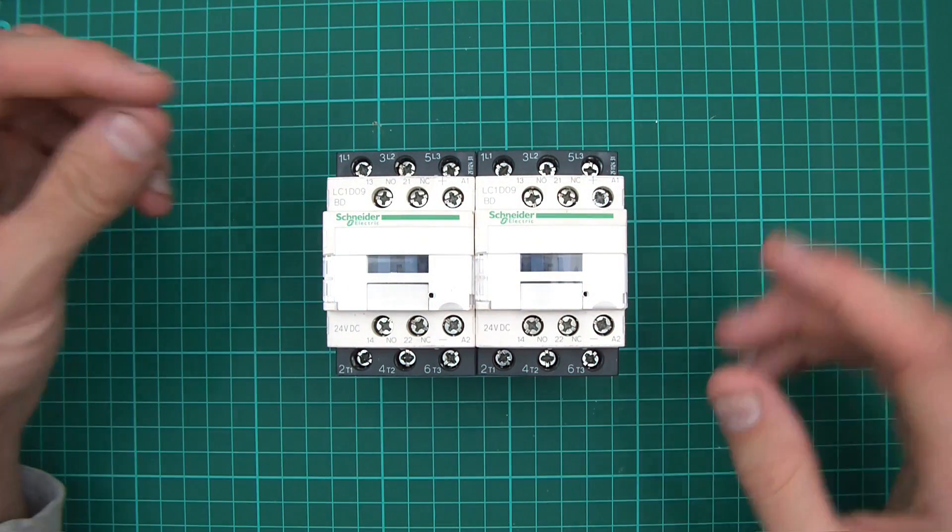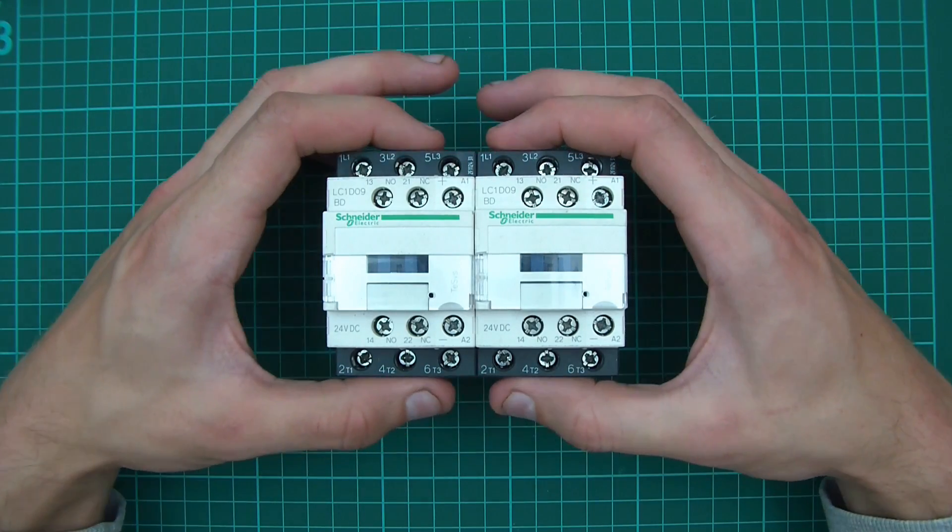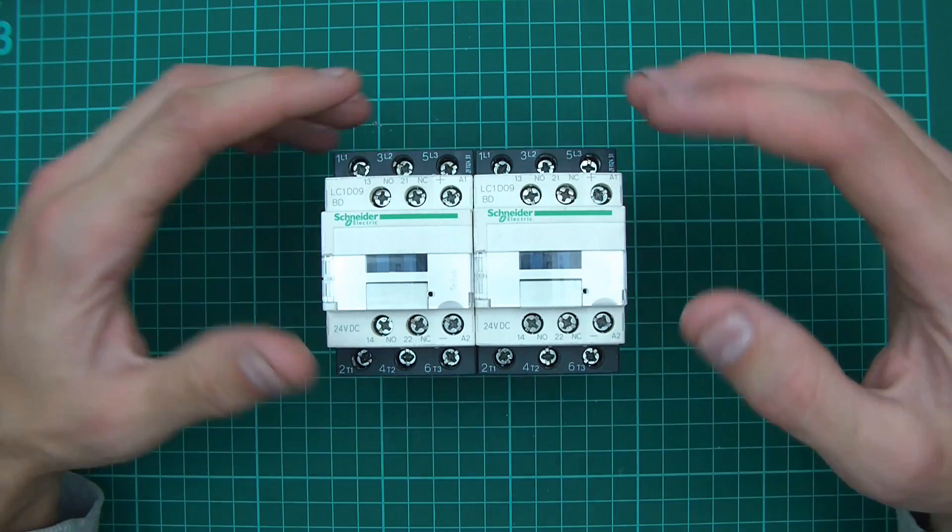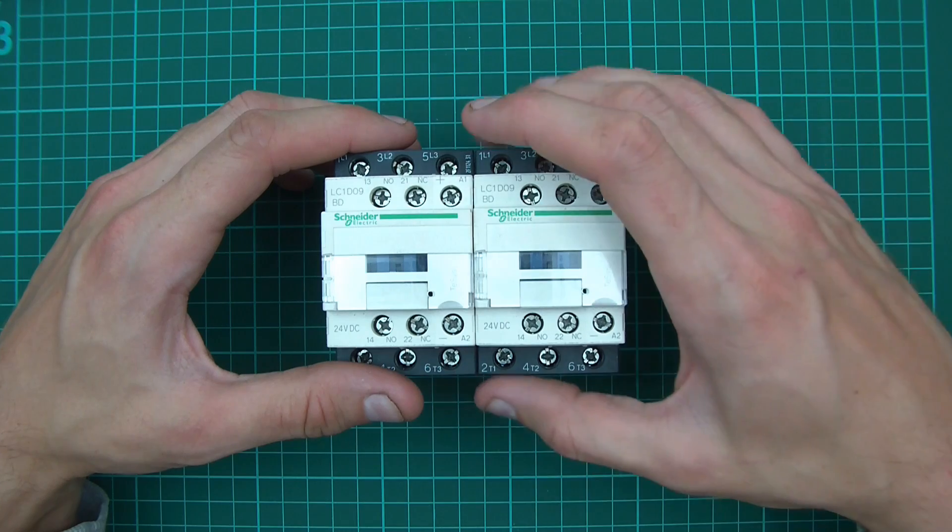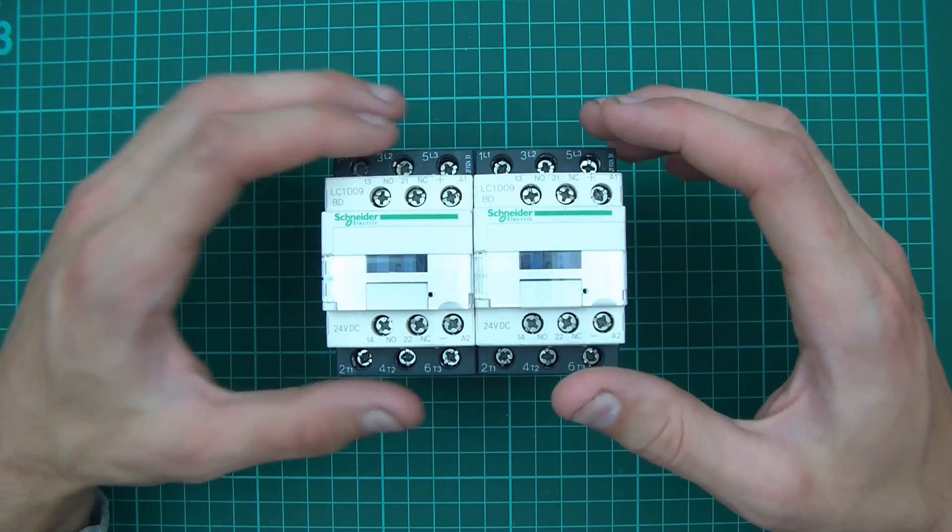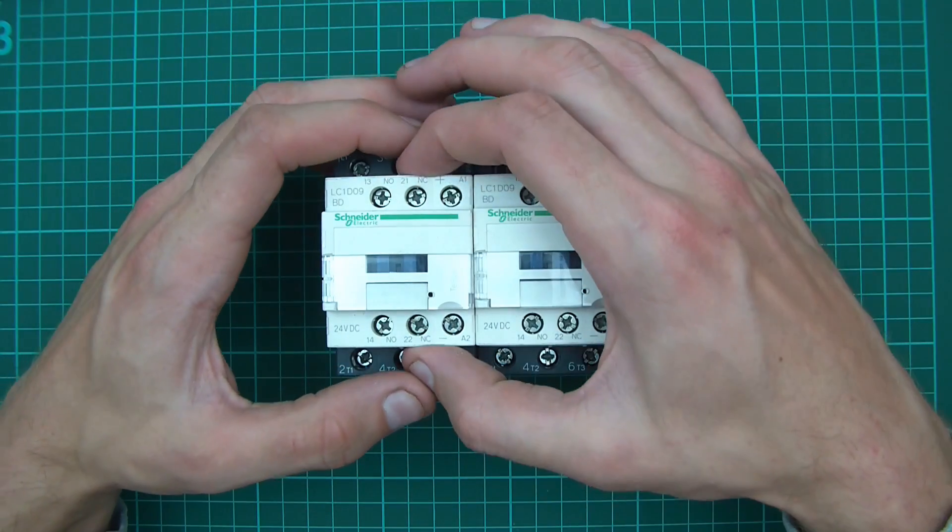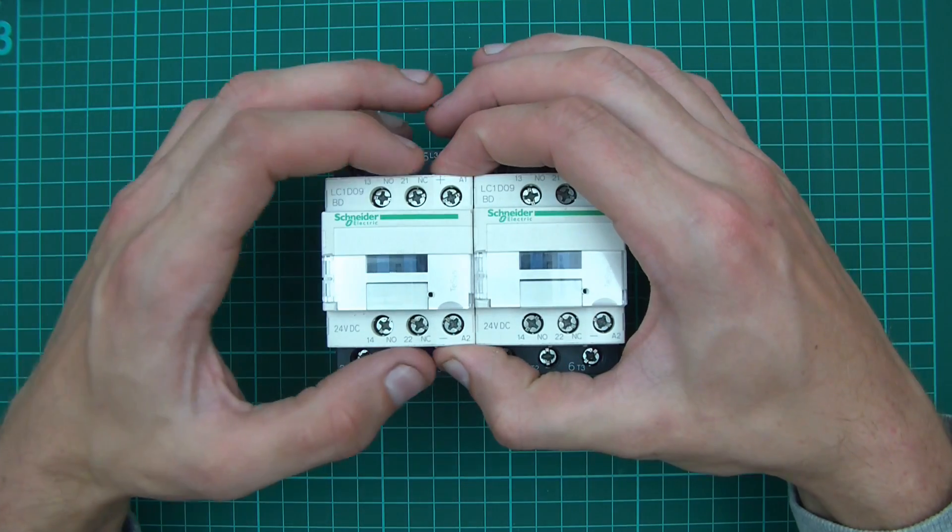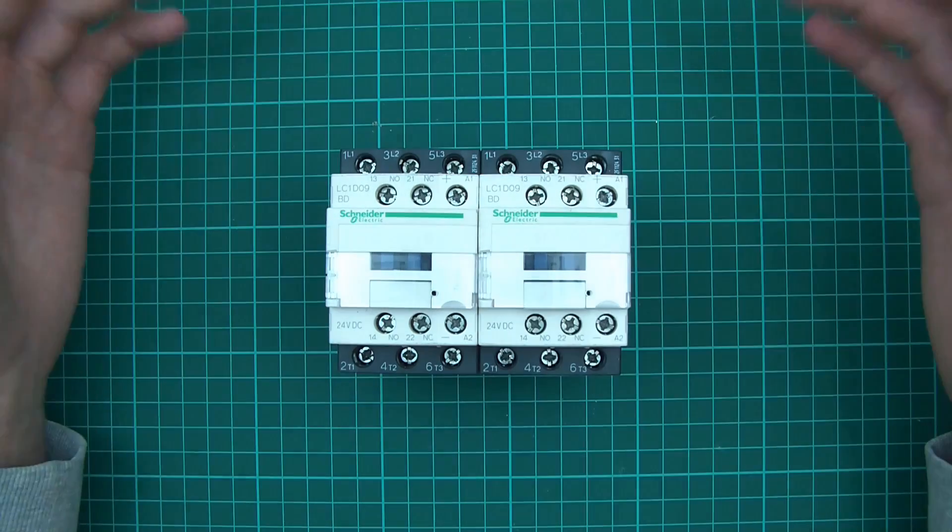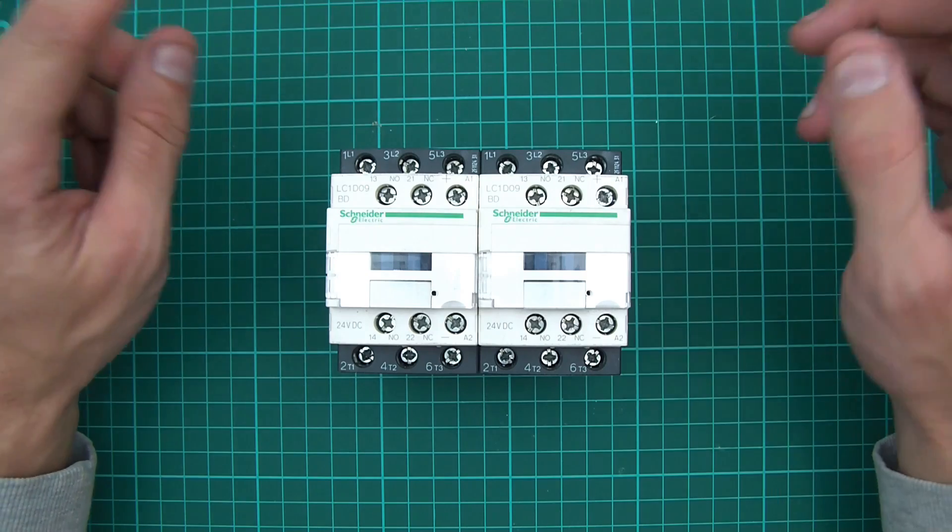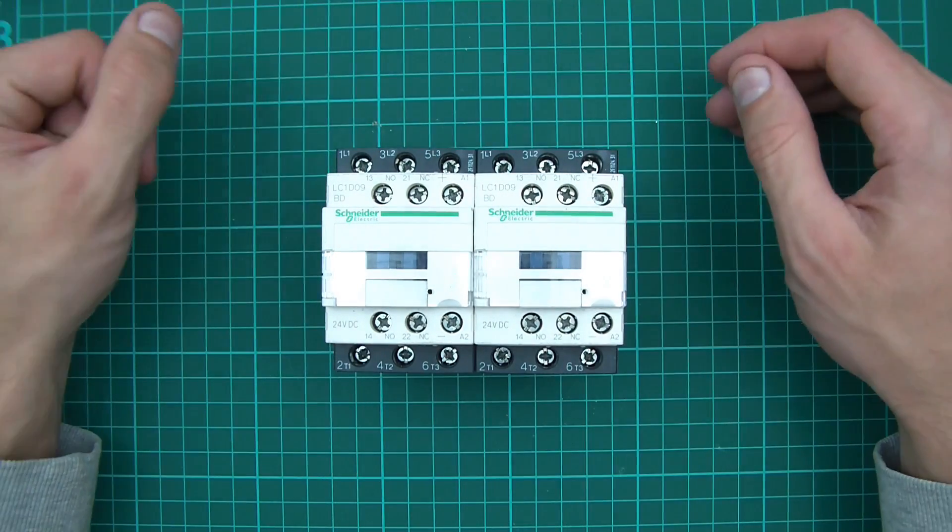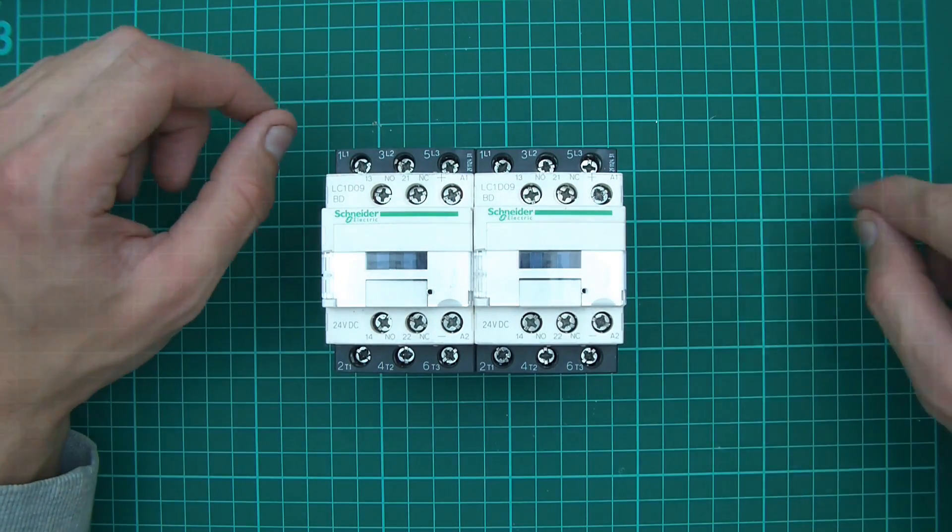These contacts here are called NO contacts or normally open contacts, and that means when there's no power to the coil these are open circuit. But there's one that says NC and that means normally closed. So this is normally closed and all the rest are normally open, but as soon as you power the coil that changes to normally open and all the rest become closed. It's like lots of relays together, although it's slightly different mechanically than a relay.